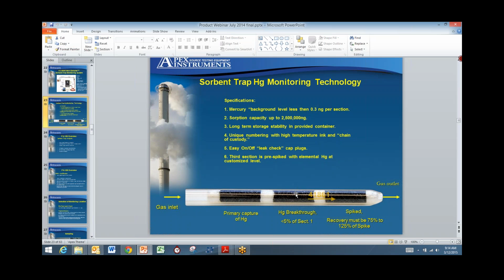Very rarely do we see any issues there, unless we have some really unique situations in terms of stack gas composition, moisture, things like that. And then finally, the third section of carbon is pre-spiked at the lab with a known amount of mercury before the traps come out to you. Then we'll do a spike recovery once we come back for analysis. Again, this is a QA/QC procedure to make sure that we haven't had any mercury loss or burning off of the mercury during the sampling time. So we can make sure that what we're catching here is a true representation of what's in the stack. If we recover between 75 and 125% of the pre-spike level, then we're within compliance of PS12B. So that's the basic anatomy of a sorbent trap.